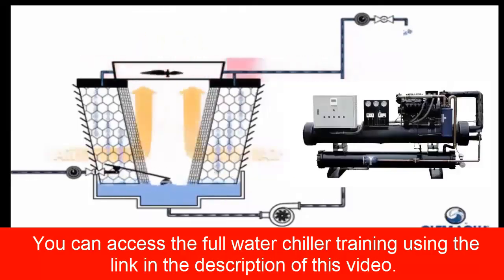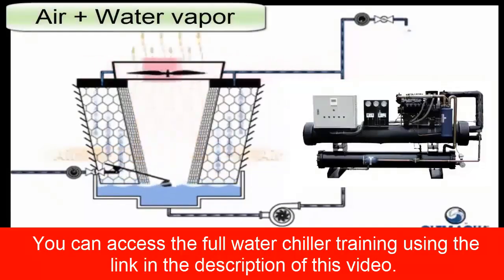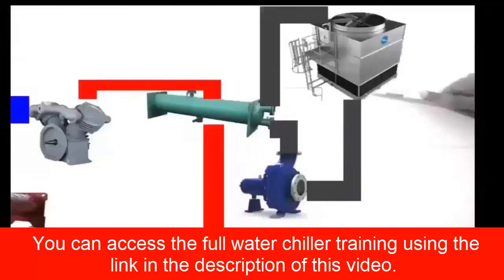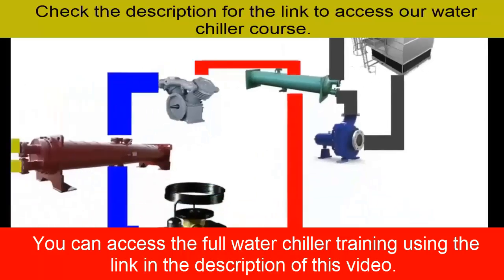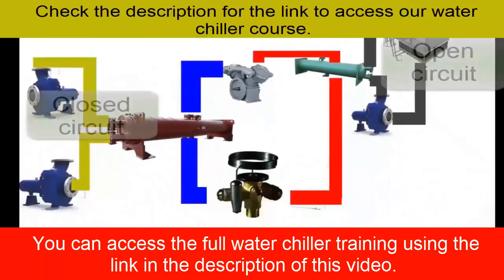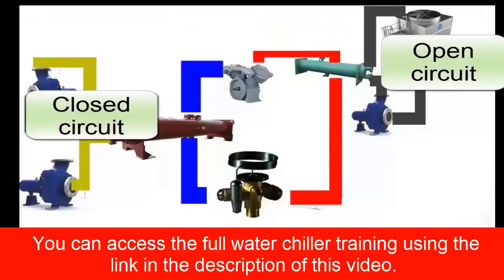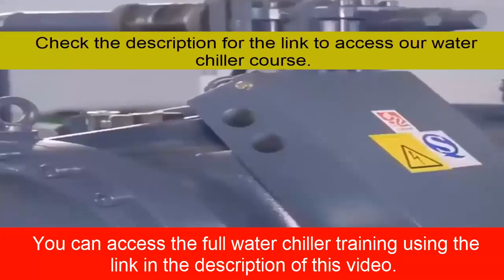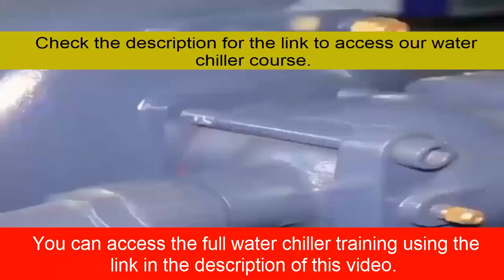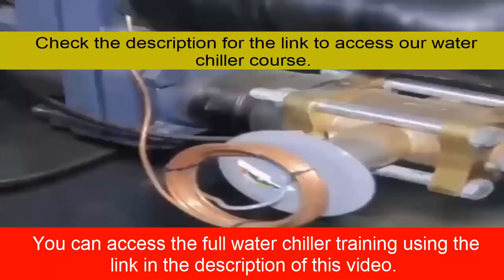Cooling tower operation. The hot water coming from the condenser reaches the cooling tower, where another heat exchange occurs with the ambient air using fans. In this process, the water releases heat to the air and cools down before returning to the condenser. The main advantage of this method is that the water can reach temperatures close to the wet bulb temperature, while air is governed by the dry bulb temperature. This means that on average, the water temperature will be lower than the air temperature, promoting better heat transfer and facilitating heat removal from the condenser. As a result, the refrigeration system operates more relieved and efficiently.